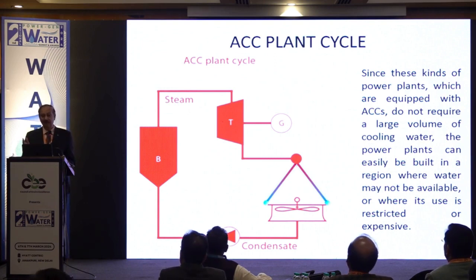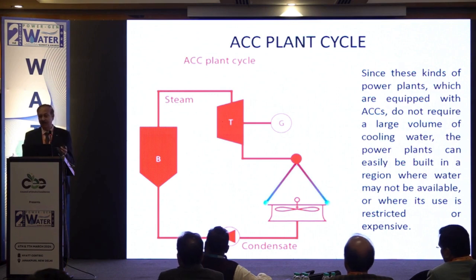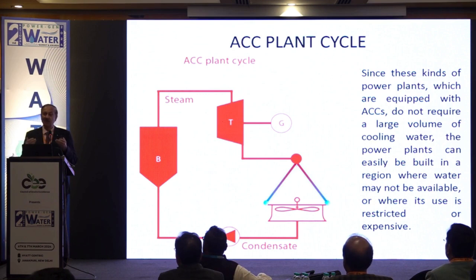is a dilemma, there is a decision to be taken, because in case you go for an ACC or air-cooled condenser, the coal consumption will slightly go up. That is, the heat rate will slightly go up and the vacuum will be poor, but water consumption will go low. In case you have a water-cooled condenser, the heat rate is better, the vacuum achieved in the condenser is better.